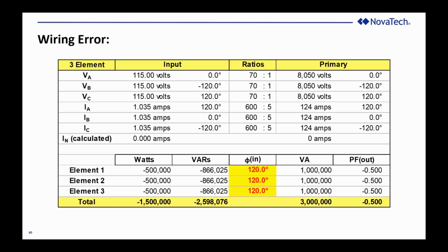So what do I see? Neutral current is normal. The watts is about half of the VA. The power factor is half. The VARs are much greater than the watts. It's not going to be twice as much because the VARs are based on the sine of 120 degrees and the watts are based on the cosine of 120 degrees, which is completely different. But the indications that that's the nature of the wiring error are still pretty clear and easy to work backwards from the symptoms to the error.